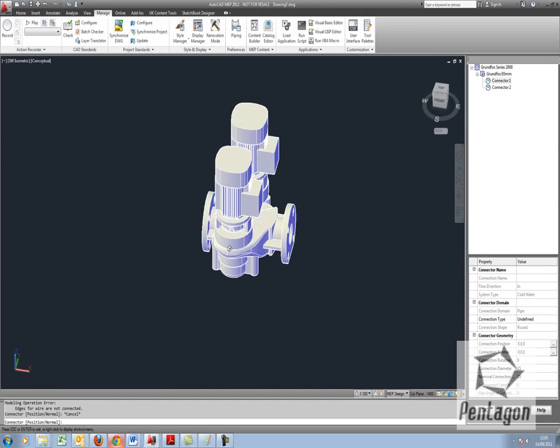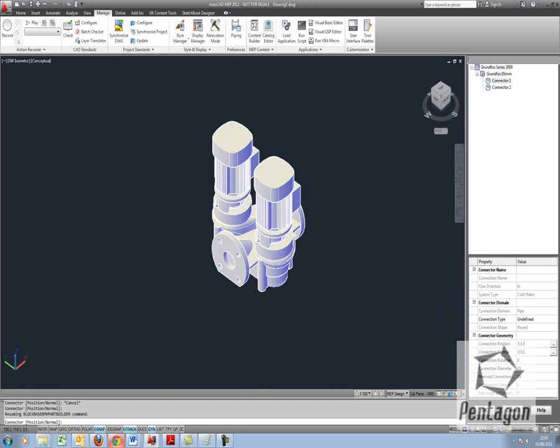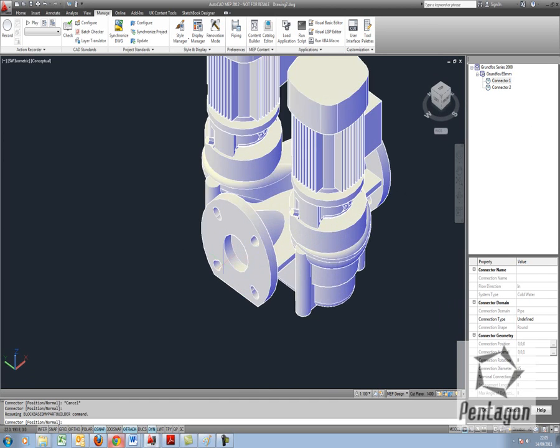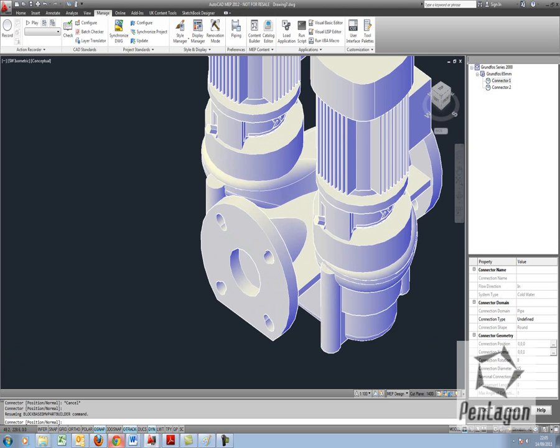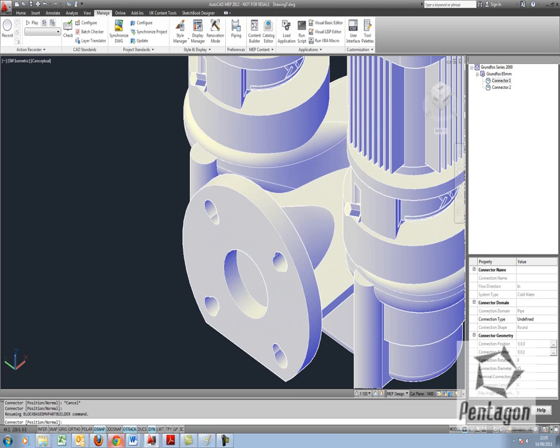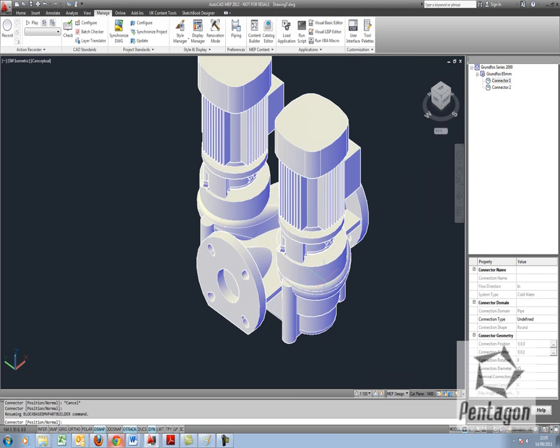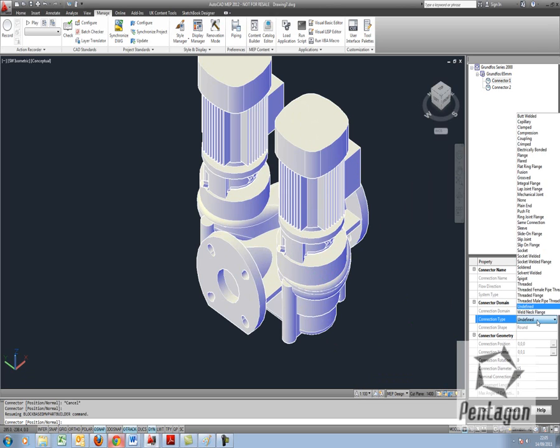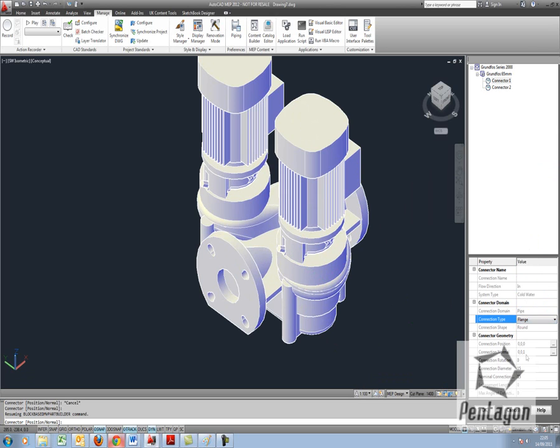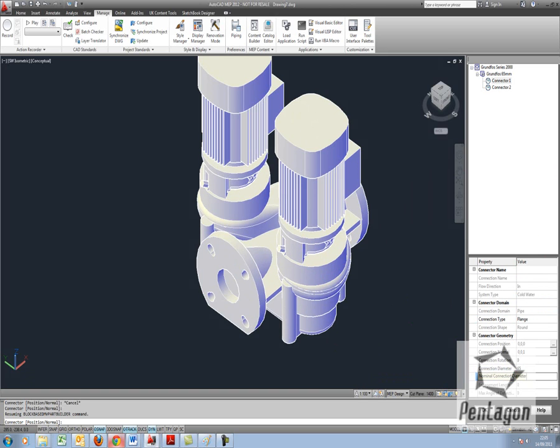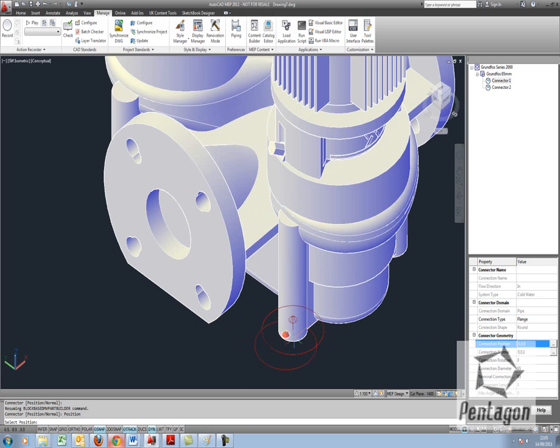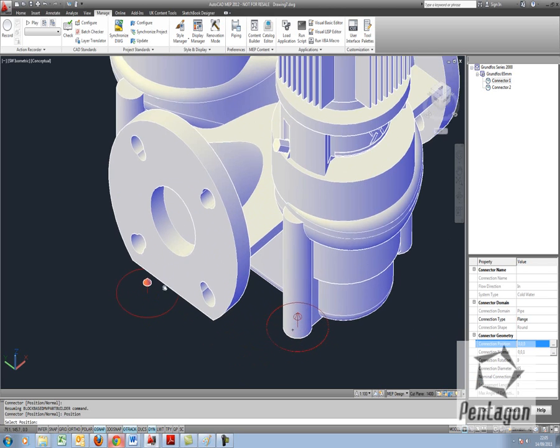So I'm going to have my two connections from my inlet and outlet. So to position this, I'm actually just going to change the settings to start with. So the connection type in here, I'm going to actually say well this is flanged. I'm going to give it its nominal connection sizes which is 65mm. In this case, and it's important to give it its connection position.